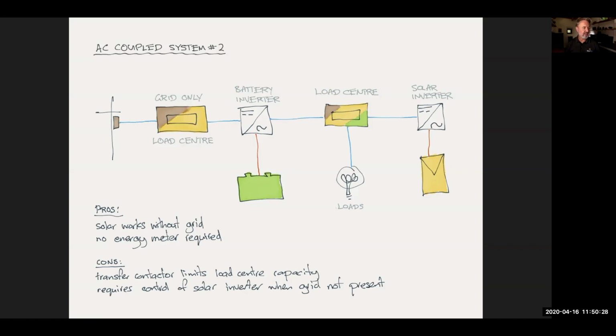The slight limitation of this design is that the internal contactor of that battery inverter will limit the maximum current you can draw from that switchboard or load center. But it's not a big deal. Many inverter systems allow you to have external contactors that you can control as well.